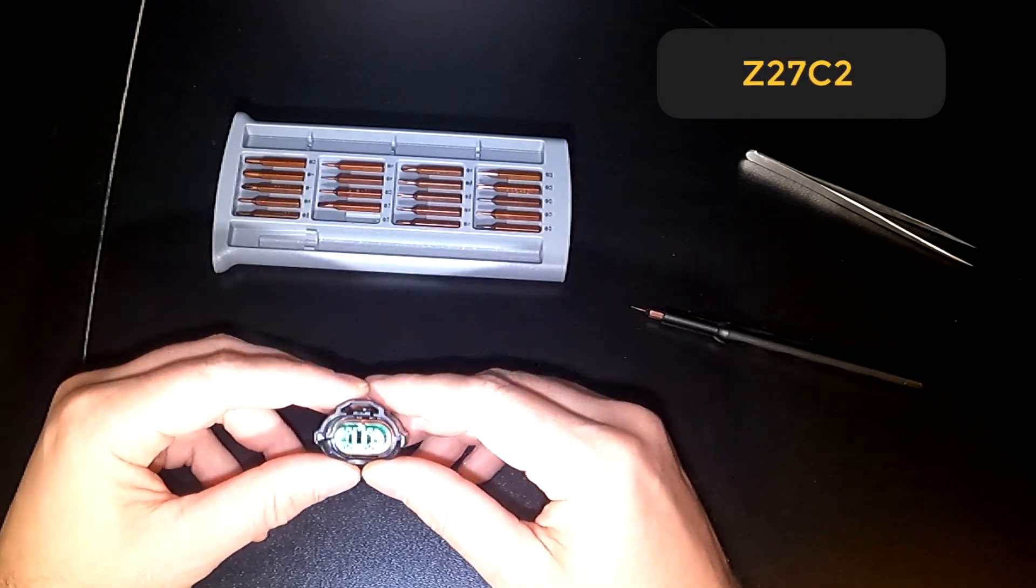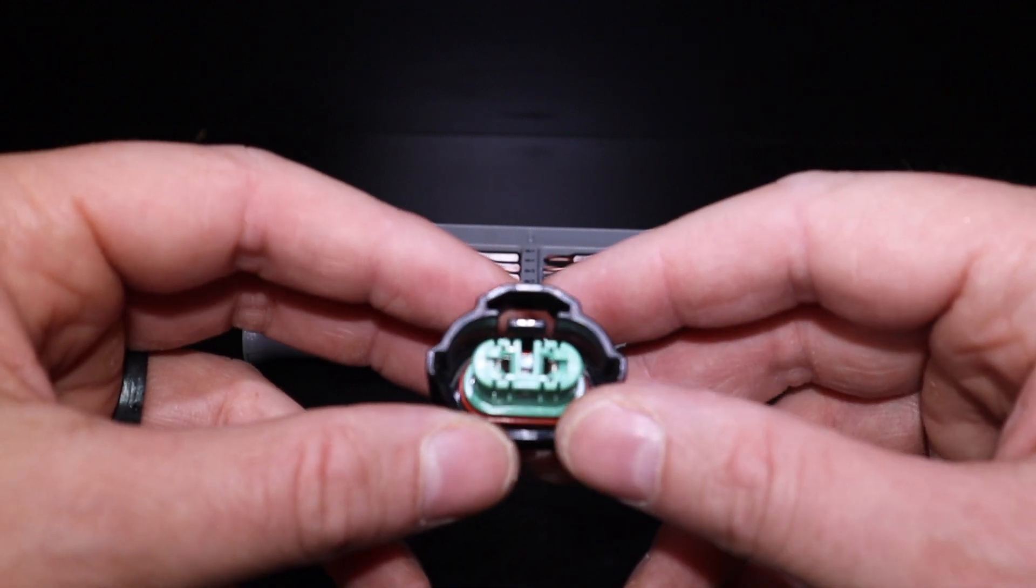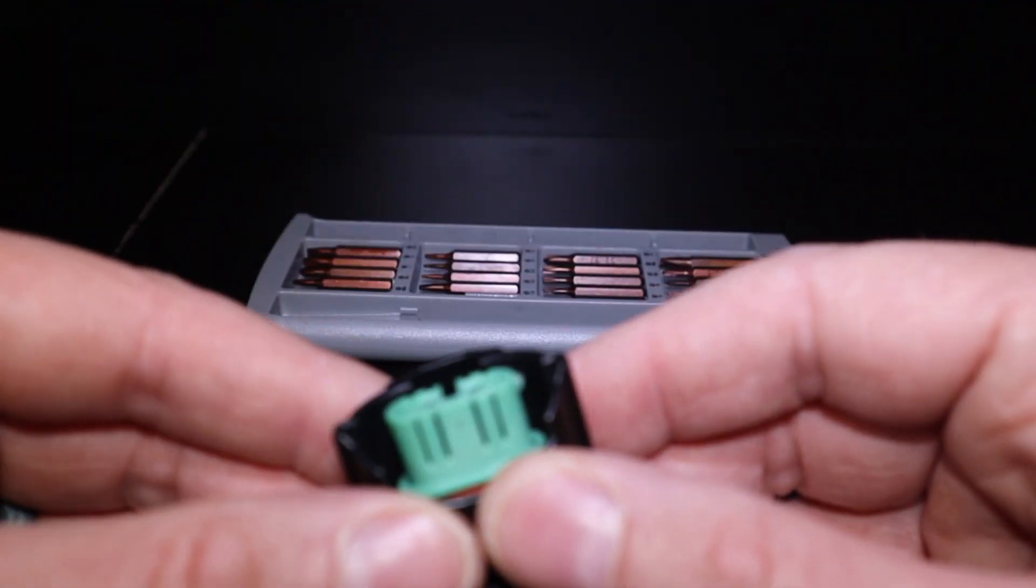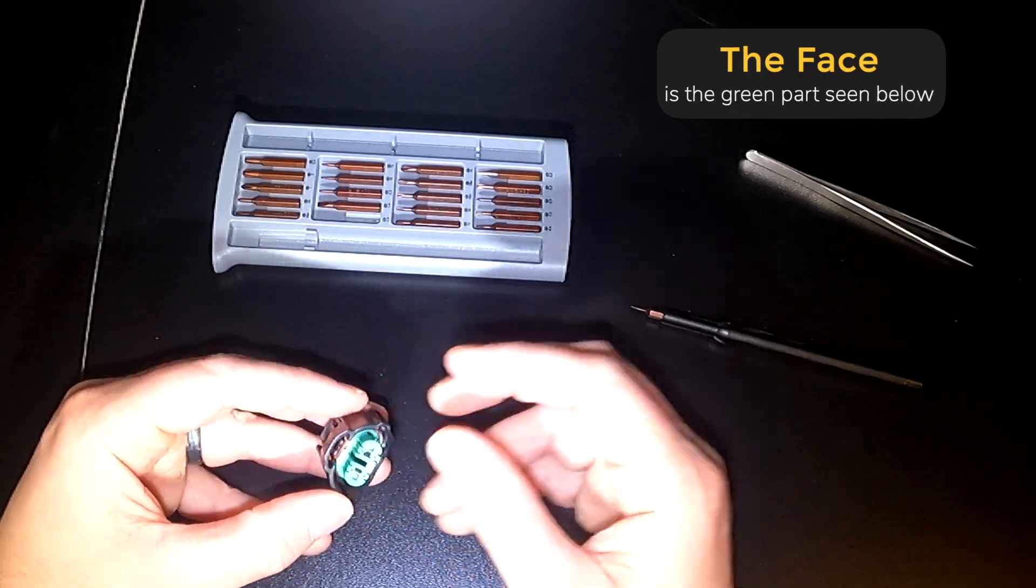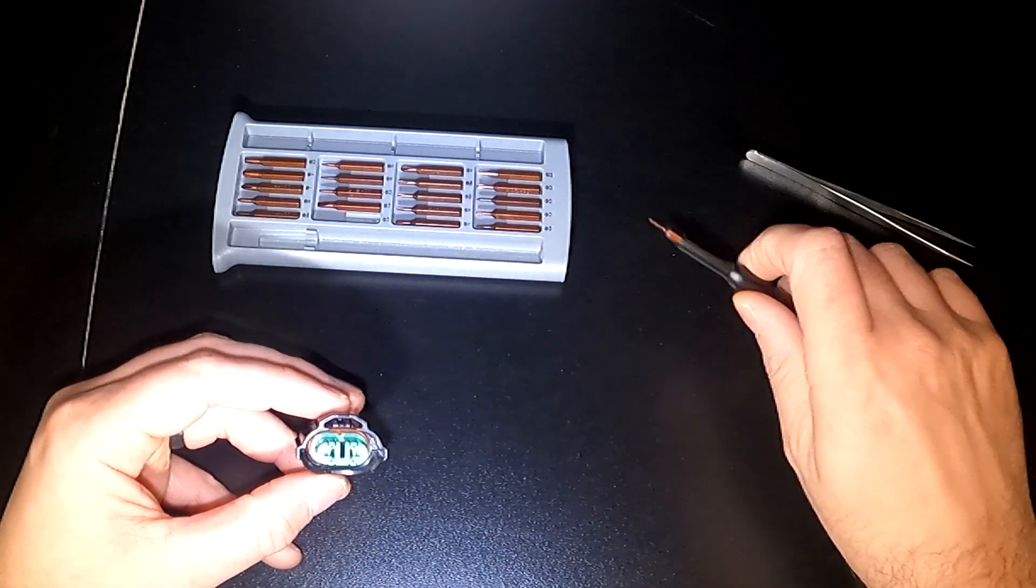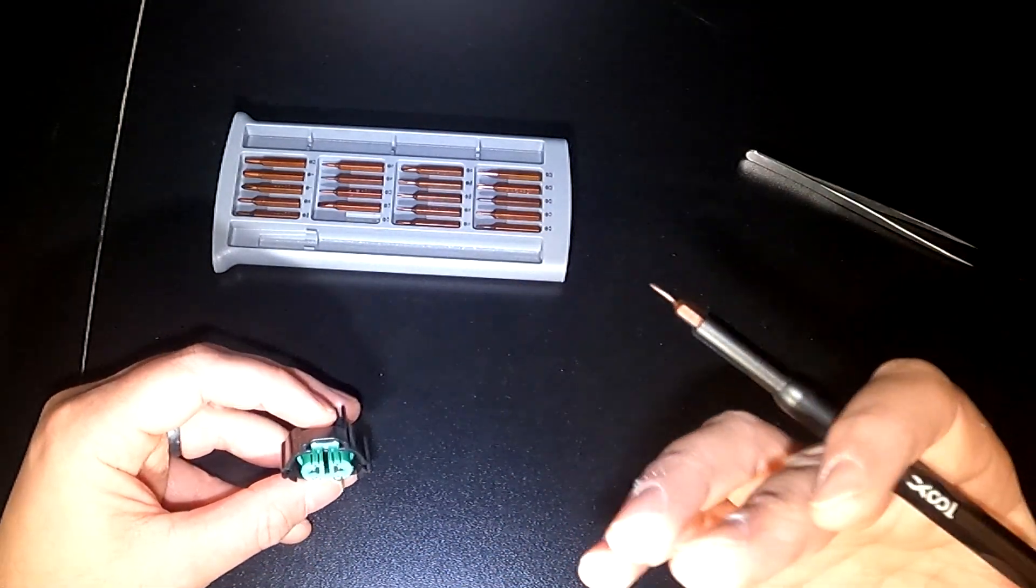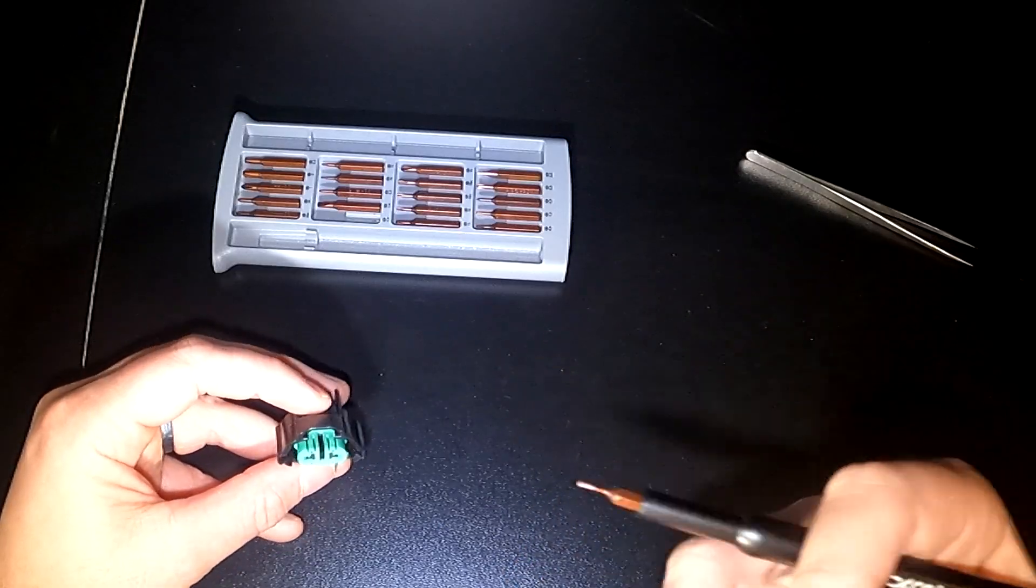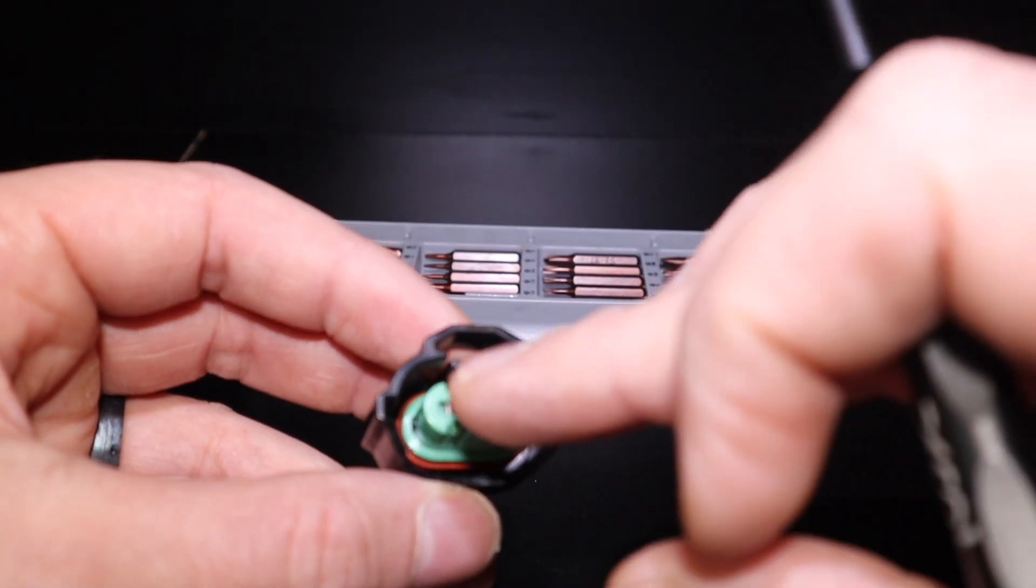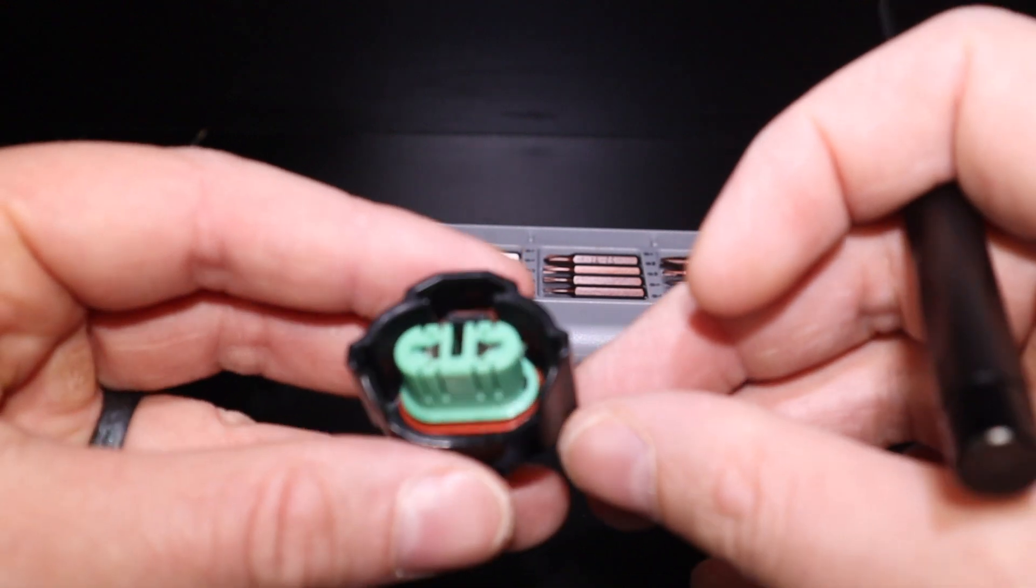The first thing you need to do when you need to do a quick de-pin or re-pin is take the front face off. And the important thing is you want to be really careful to do that because if you're not careful or if you're in a hurry and you're too rough, you could easily break these little housings and these plastic catches.